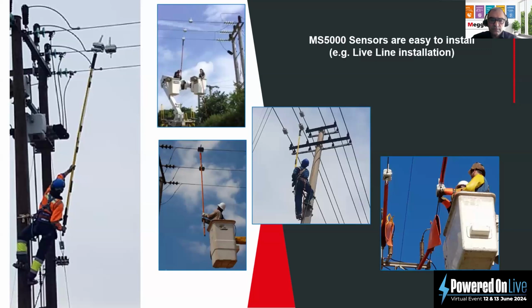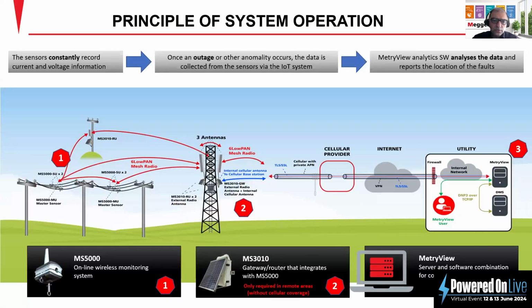Sensors can be installed on the live line by using short and longer sticks, and also by using high voltage gloves. As for the principle of operation, sensors are normally provided in sets of 3 for 3 phases and distributed in the network. Sensors constantly record current and voltage information, and once an outage or other anomaly occurs, the data is collected from the sensor via the IoT system, and they send this data to the MetryView software for analytics.